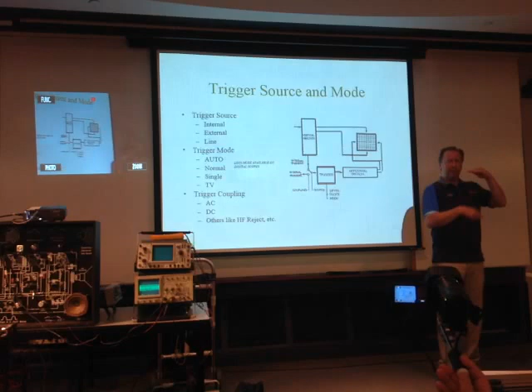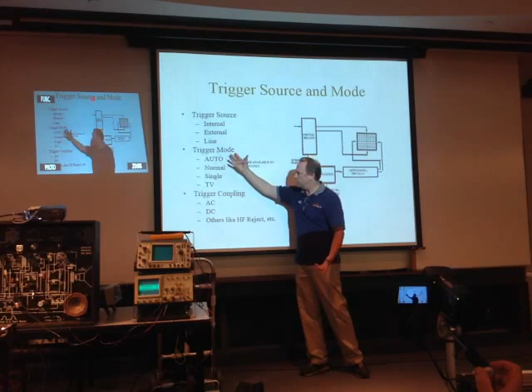So auto trigger is going to look for that condition, and if it gets impatient, it says, you're not giving me a trigger, I'm sending a sweep anyway. But it allows you to get something going across the screen so you can see what's happening. Maybe you've got to adjust the trigger to see it. So auto trigger is where you're normally going to leave things. You could use normal trigger, but most of the time auto trigger will be just fine.